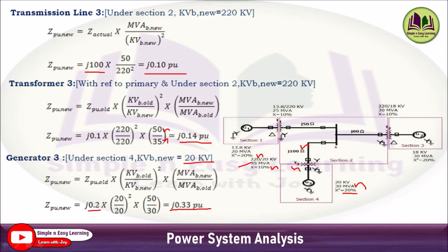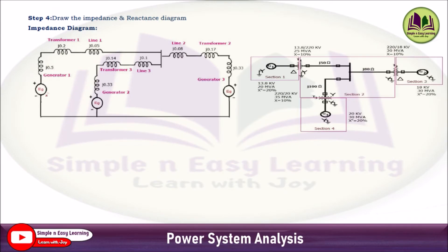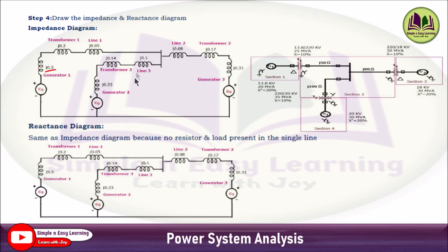In the impedance diagram: generator G1 reactance j0.5, transformer T1 j0.2, line 1 j0.05, then a central junction with line 2 j0.08, transformer T2 j0.17, generator G2 j0.33, and from the junction: line 3 j0.1, transformer T3 j0.14, generator G3 j0.33. Since resistance and shunt capacitance are not given, the impedance diagram and reactance diagram remain the same.